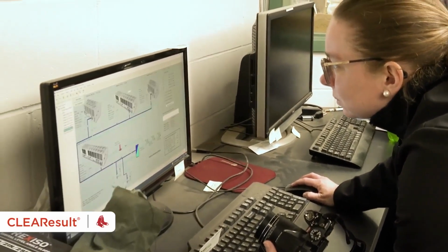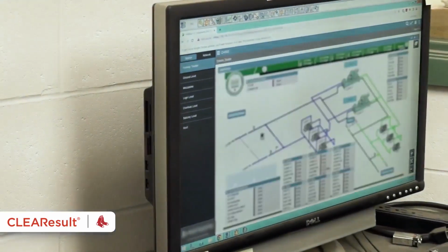One thing we noticed was their building management system does have scheduling capability. So if we feel some equipment is running when it doesn't necessarily need to be, we can shut things off, apply a schedule to them to conserve energy, but definitely some room for improvement that we can focus on.